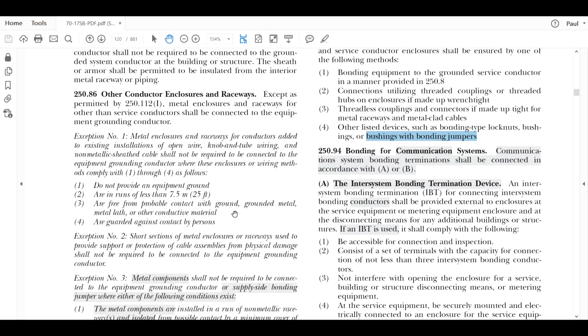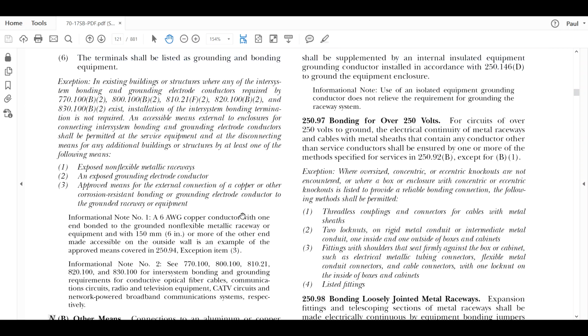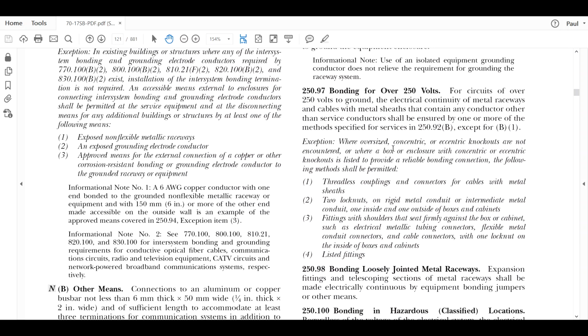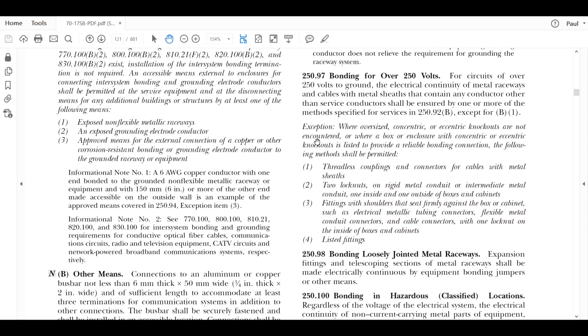So under the exception to all of that, it's the exception to go to 250.92. So I don't want to go there. If I'm not dealing with concentric, eccentric, and knockouts, I'm punching my own holes, guys, then I don't have to go to 250.92(B). I can use the exceptions right here. And those are a purely punched hole, or maybe if you did have concentric or eccentric, all of the knockouts came out and it was the right size you needed, then it's kind of no different than if you punched it out.